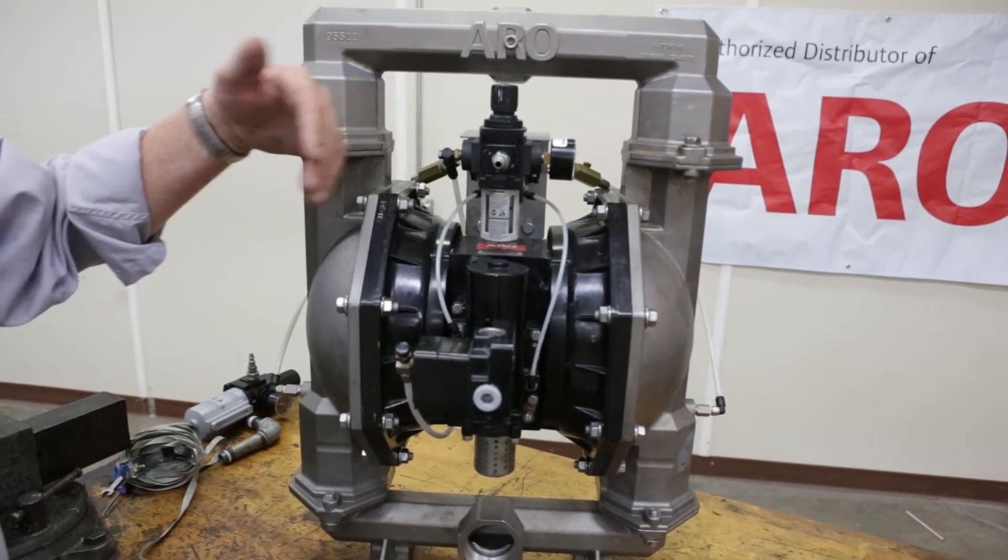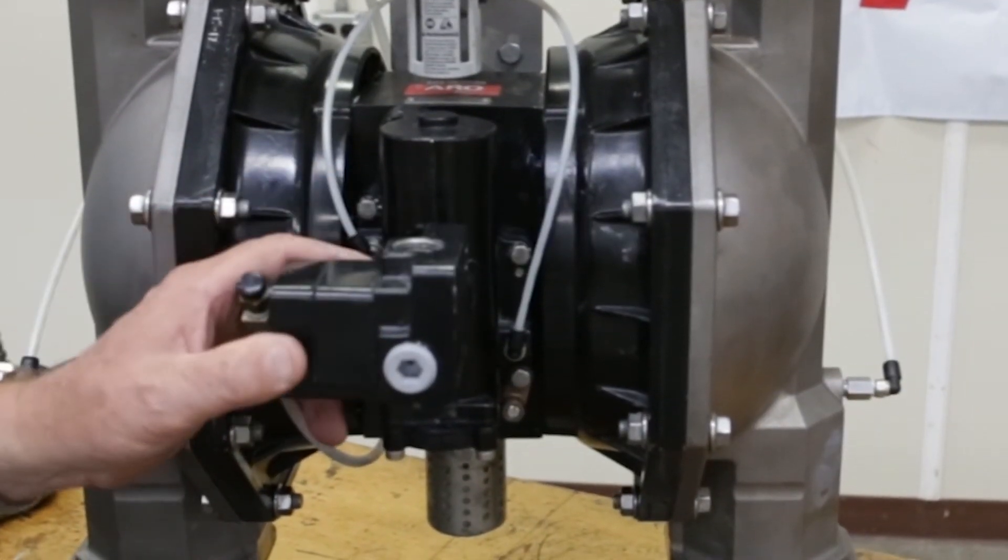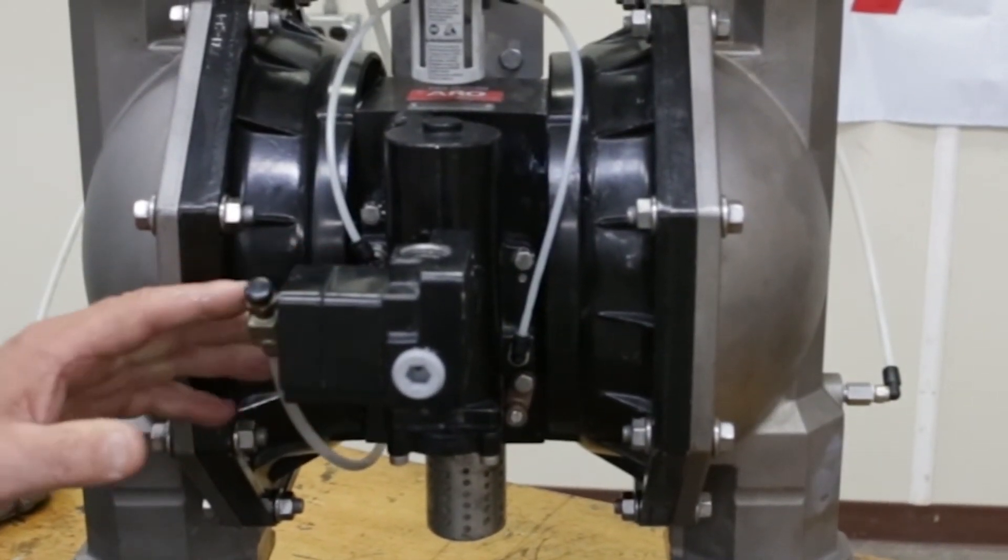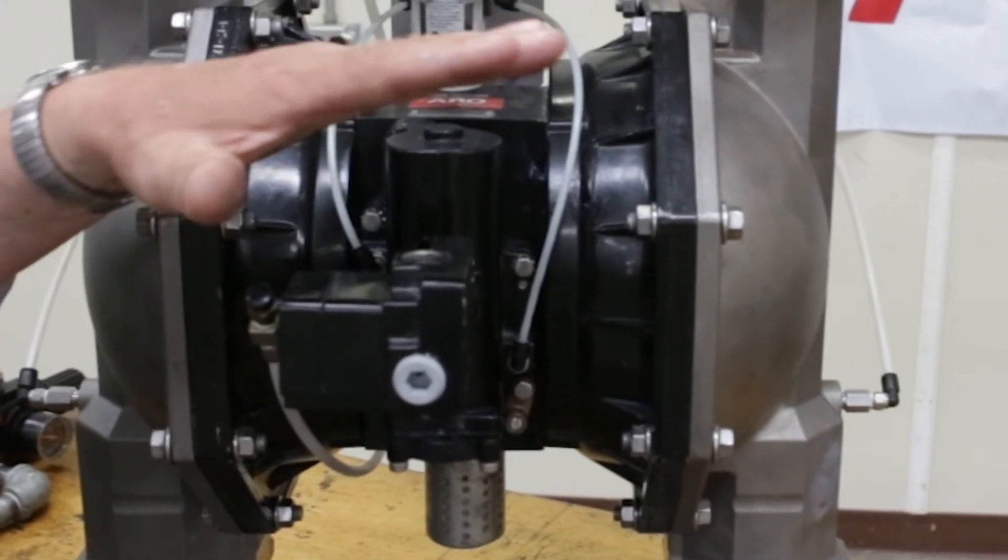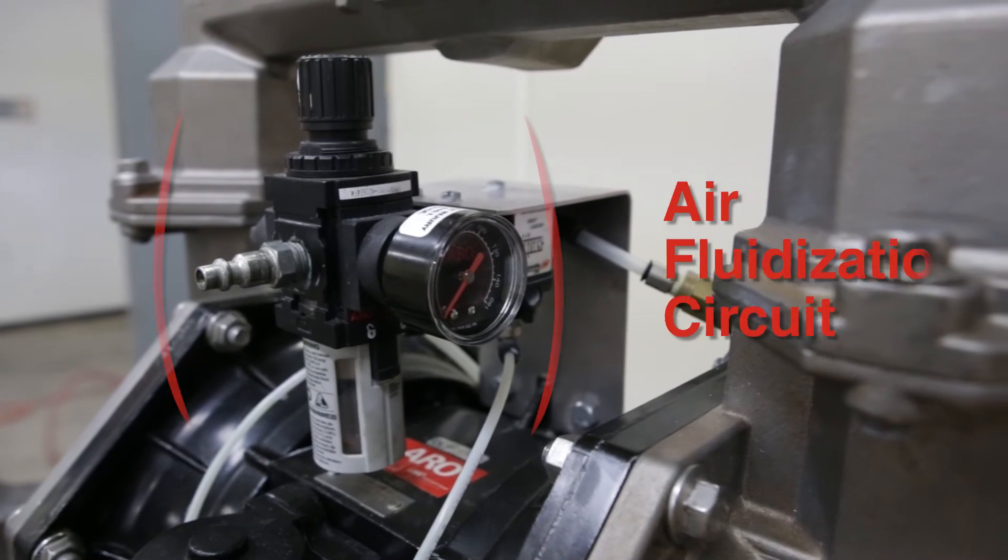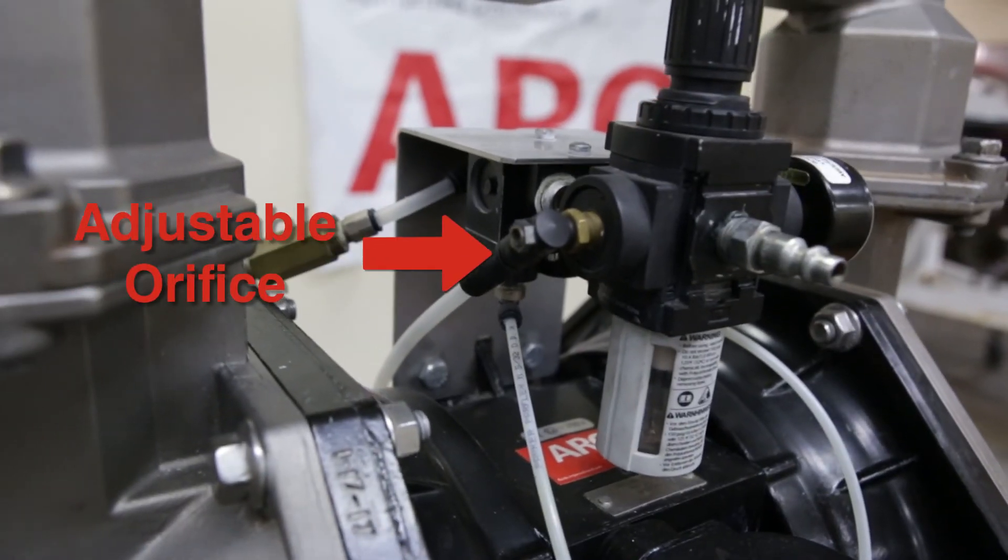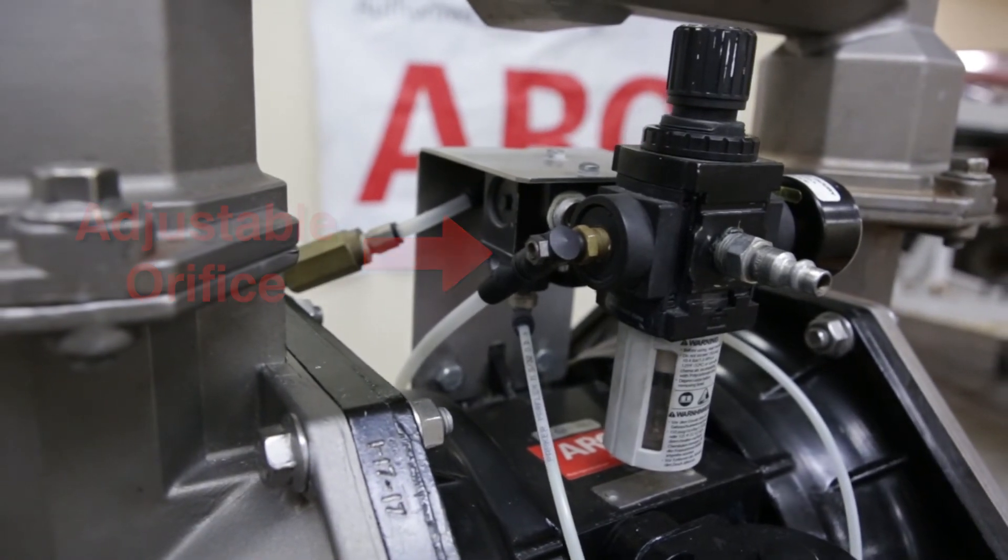We've added some additional components to the pump to make this work. On the front of the pump is the main air supply. This is an ARO H-series valve, which powers the diaphragms and allows them to reciprocate. The second component is the air fluidization circuit. This is made up of a mini regulator and has an adjustable orifice and an alpha four-way valve on the backside.